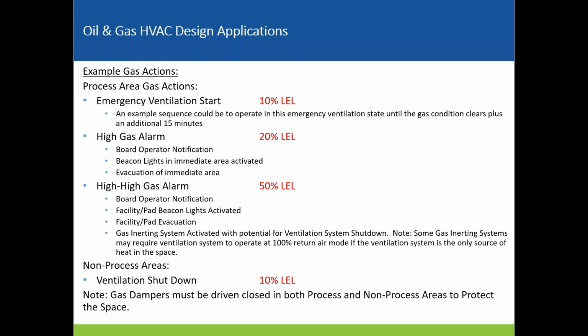We found from some of our studies that if it's not warm in there, it's just going to puddle on the floor. So something to consider. And then if it's a non-process area or an unclassified area, you know, we hit that 10% LEL, probably at a gas detector at the discharge of the air handling unit, and shut the ventilation down and close it down. There shouldn't be any gas in the space causing the LEL. It should be coming from outside.